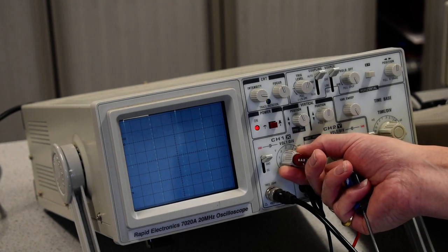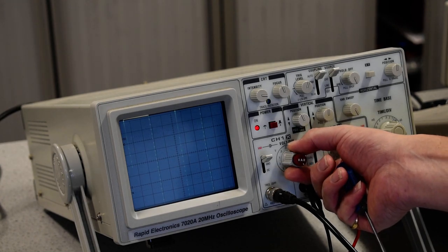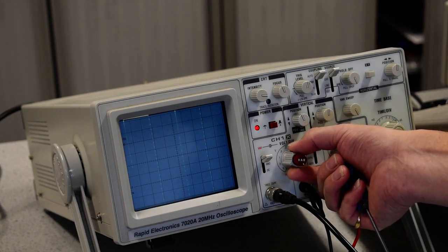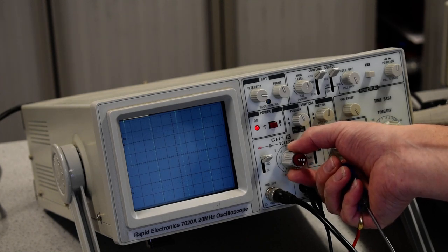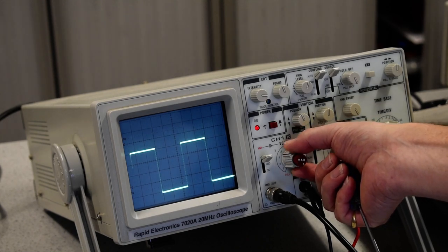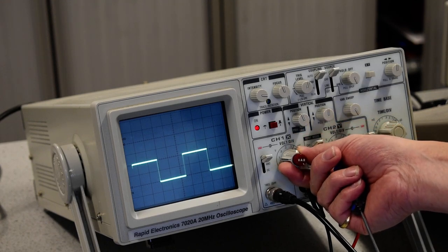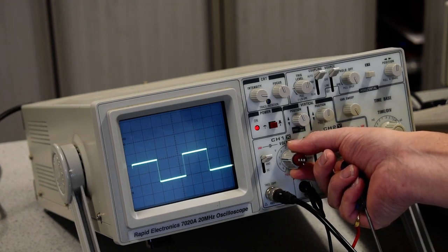If we go down a scale, the waveform is too big on the screen to measure. You cannot measure accurately because we're going off-screen. We don't want to go up a scale because the waveform is then too small.